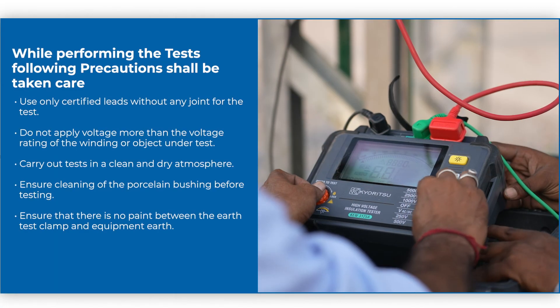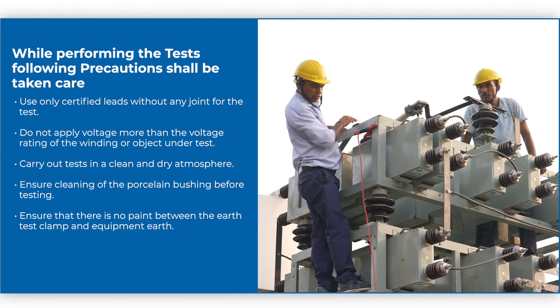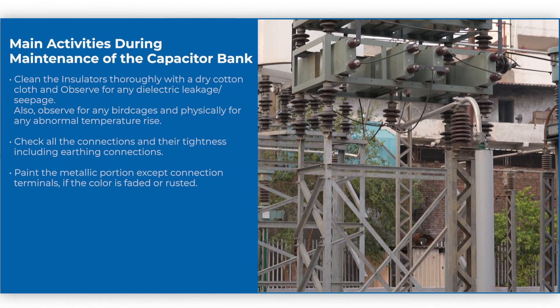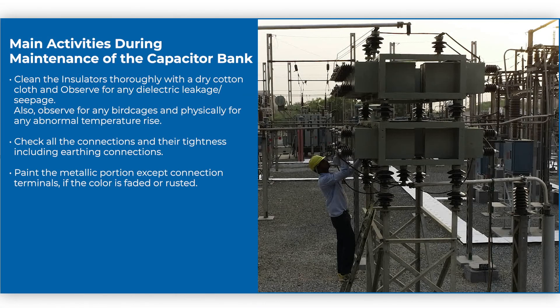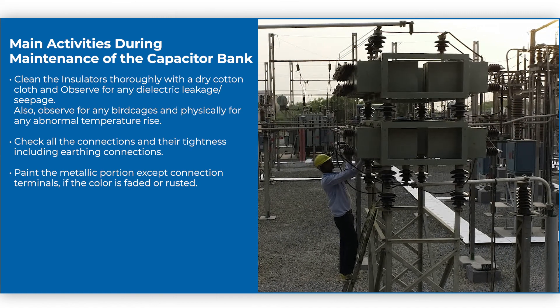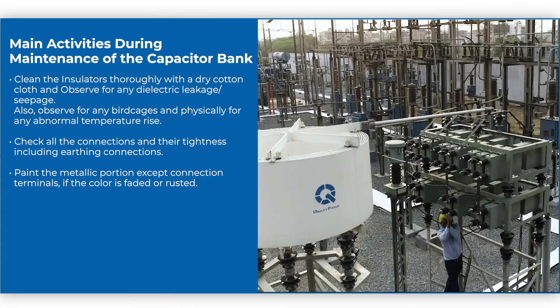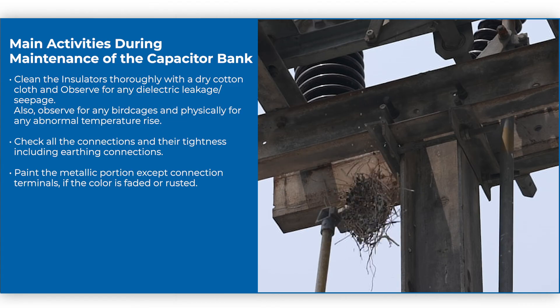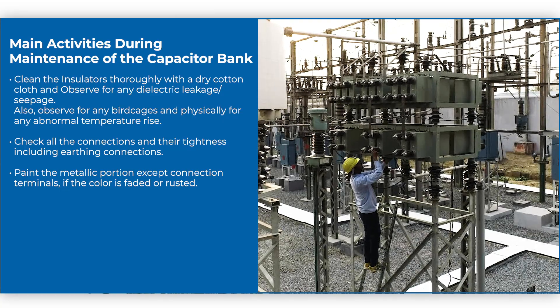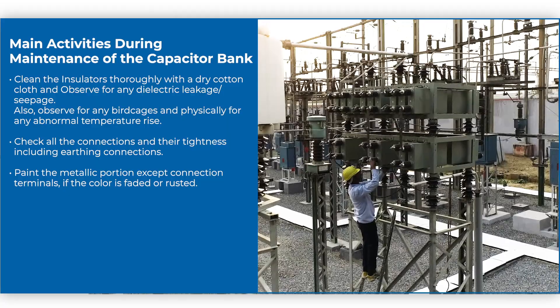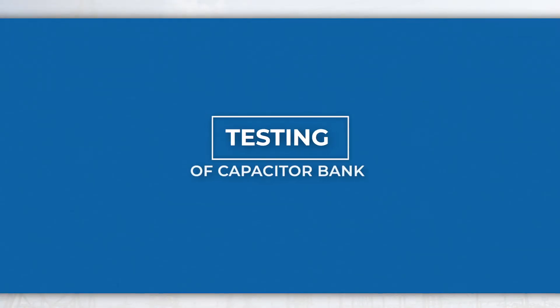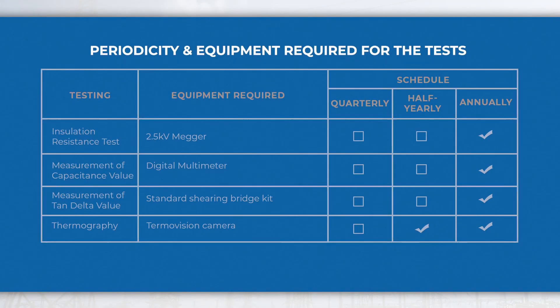Also ensure the use of personal protective equipment for safety, such as electrical grade shoes, helmets, etc. During maintenance of the capacitor bank, clean the insulators thoroughly with a dry cotton cloth and observe for any dielectric leakage or seepage, also observe for any bird cages, and check for any abnormal temperature rise. Check all connections and their tightness including earthing connections, and paint the metallic portions except connection terminals if the color is faded or rusted.